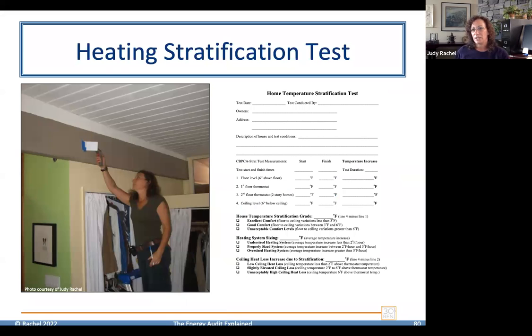Heating stratification is one of the main tests that we can and should be doing on the heating system. It's basically a scorecard for three things about the heating system and the house. It tells us whether the heating system is providing thermal comfort in the house. It gives us a score of unacceptable, good, or excellent comfort level in terms of how the heat is actually mixing in the house.